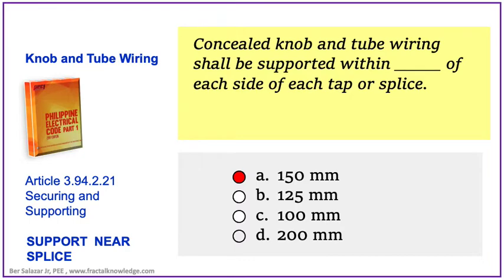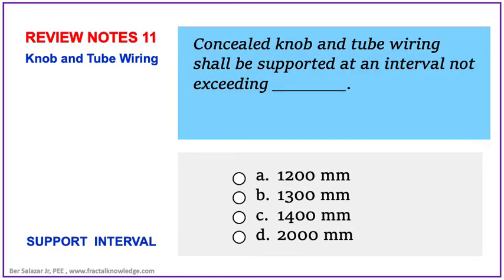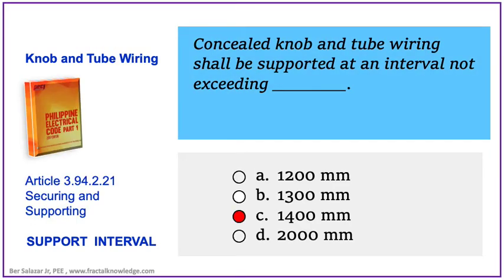Another possible problem asks: concealed knob and tube wiring shall be supported at an interval not exceeding blank. The choices are 1.2 meters, 1.3 meters, 1.4 meters, or 2 meters. The keyword here is 'support interval.' The answer is letter C: 1.4 meters or 1400 mm. Knob and tube wiring shall have this support interval.